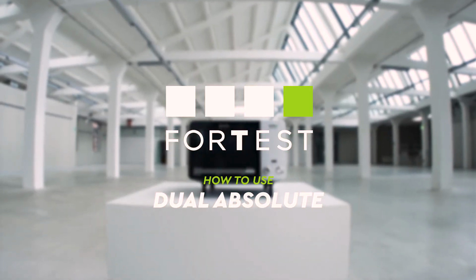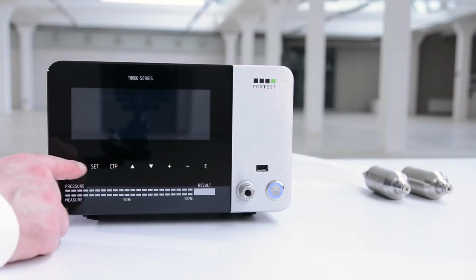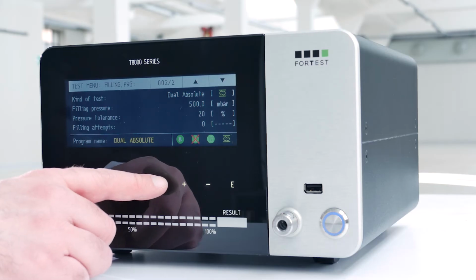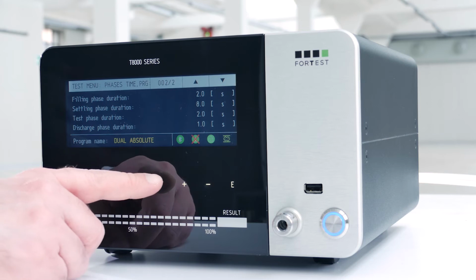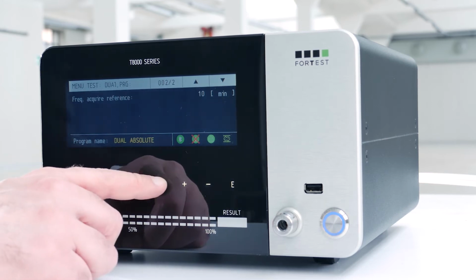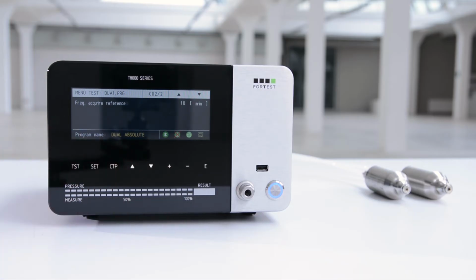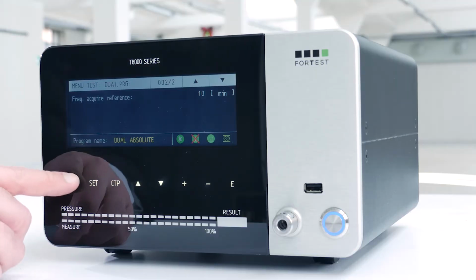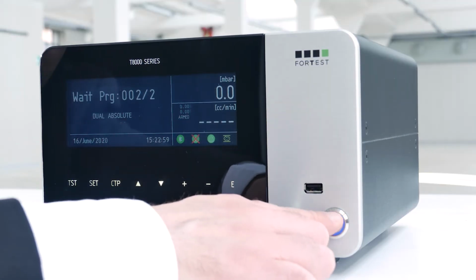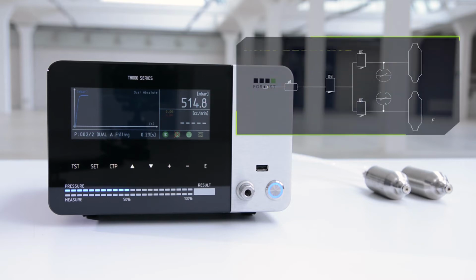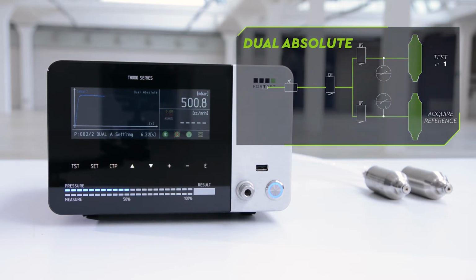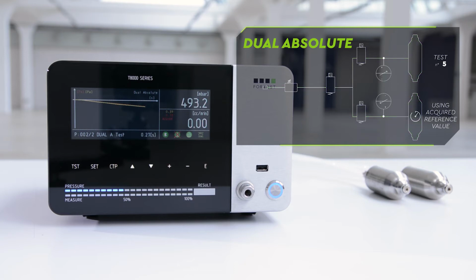The dual absolute mode represents an improvement over the usual differential systems currently on the market from the point of view of repeatability and the influence of thermal and mechanical variations on the reference part due to continuous filling and emptying. In this mode, the instrument performs a measurement of the differential pressure drop between a test part and a reference part. The difference with the normal differential system is that a measurement is performed on the reference part at programmable intervals and not continuously test after test.